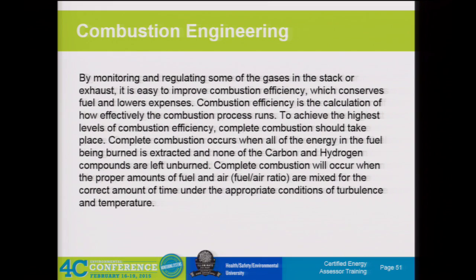The combustion efficiency is specifically how efficient we are at converting the energy in the fuel to usable energy for our process. Are we getting unburned carbon out of that, or are we generating too much CO? That's the combustion efficiency. Then you get into the overall system efficiency—how do we transfer that heat into the usable mediums that we want? That's a whole other efficiency equation in the process.